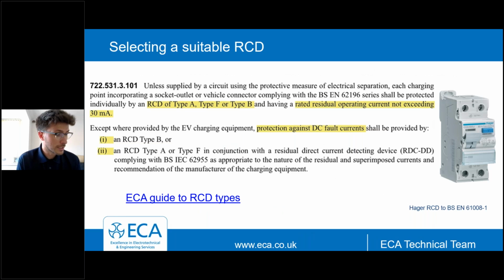Okay, so just following down onto the next regulation within BS 7671 here, so sticking on page 327, and this is again looking at selecting a suitable RCD. So we already know we need a device that switches all the live conductors, but there are additional considerations that you need to look at when selecting your RCDs. So it tells us within 722.531.3.101 that unless supplied by a circuit using the protective measure of electrical separation, each charging point incorporating a socket outlet or vehicle connector complying with BS EN 62196 series shall be protected individually by an RCD of type A, type F, or type B, and have a rated residual current or residual operating current, not exceeding 30 milliamps.